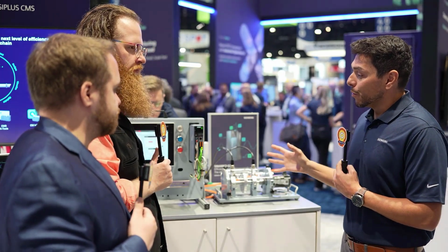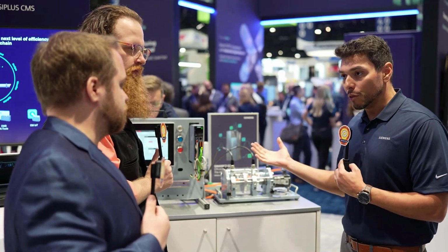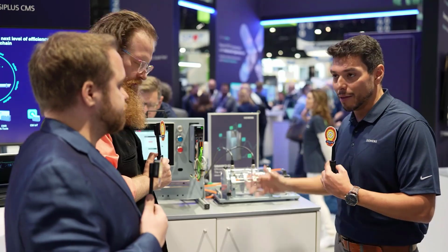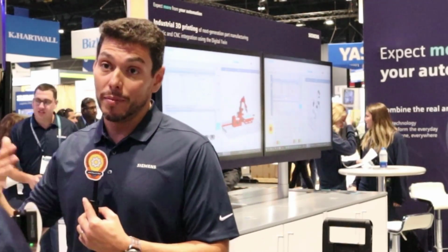Then it gives you precise mechanical signatures of those most common vibration faults that you may see in the field: unbalances, misalignments, bearing issues. A vibration specialist with a trained eye, with the knowledge of looking at those signals, would know now, they can answer the question, what happened or what might be leading to a potential failure. You probably have a loose torque on one of your motor mountings or bolts. Go there and retorque it. Or the bearing on your drive end motor is going bad. Yes. Do a root cause analysis and be prepared for maybe six months down the road to do a planned shutdown maintenance service on the machine.